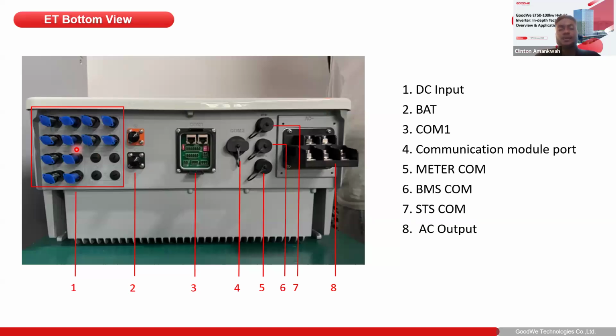So for the 40, 50 kilowatts, the highest recommended voltage is around 850 volts. With this, you have a very wide voltage range, giving you the assurance that you can easily integrate even higher PV power models in your system design. Now, on the second label, we also have the DC input for battery. We have the battery DC input slots, positive and negative.